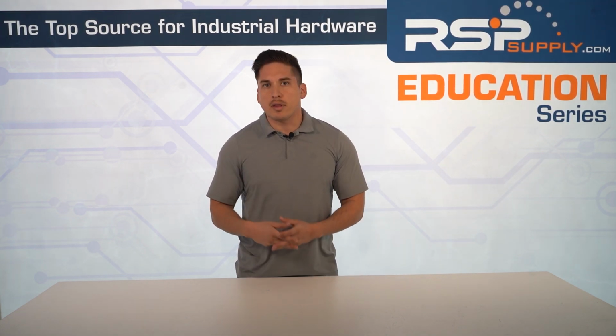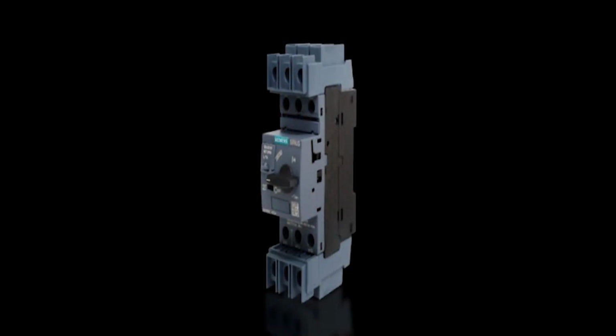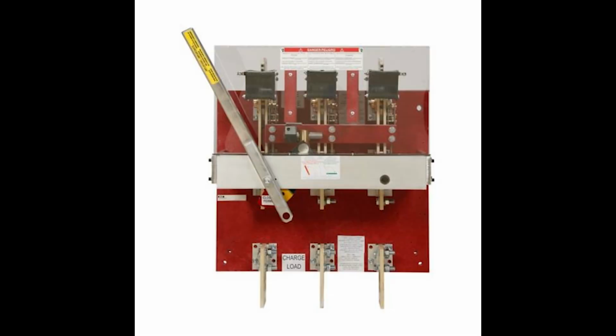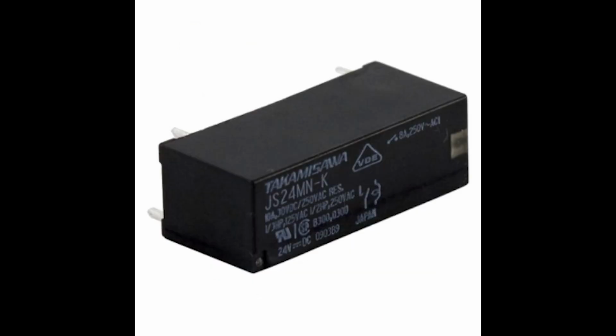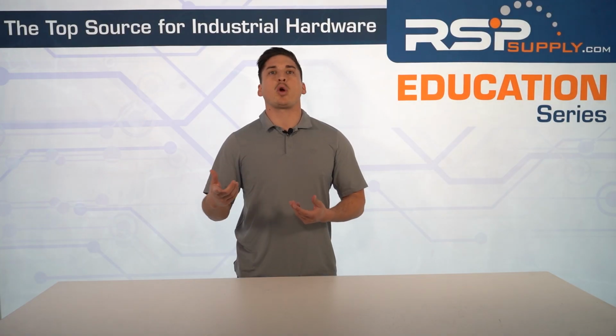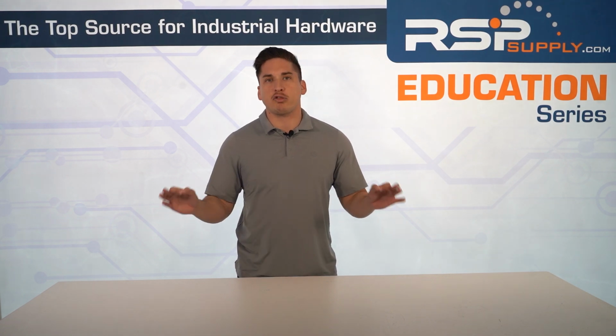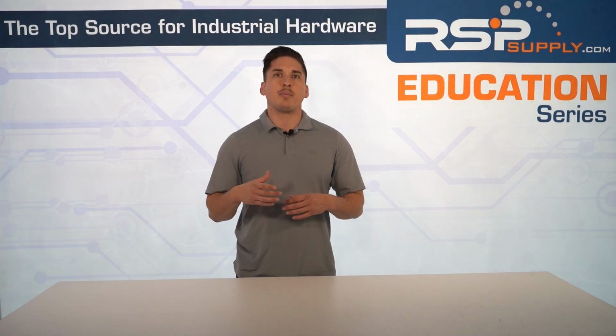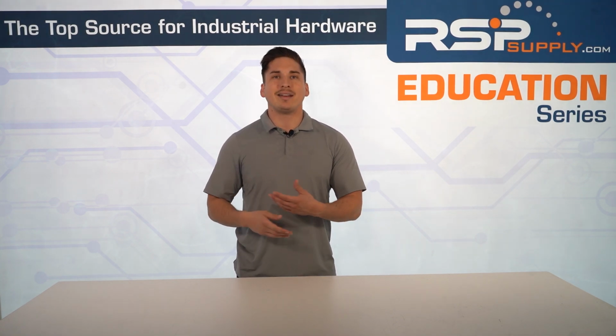Now let's break down the major components that make up a switchgear assembly. Let's start with circuit breakers. These automatically interrupt current flow during a fault to protect the system. Disconnect switches. These are used to manually or remotely isolate circuits, making it safe to perform maintenance. Relays. Relays monitor current entering and exiting the system. If imbalances are detected, which indicates internal faults, the relays trigger switchgear breakers to disconnect the transformer. Switchgear relays also manage overcurrent conditions to keep the transformer from overheating or winding damage.